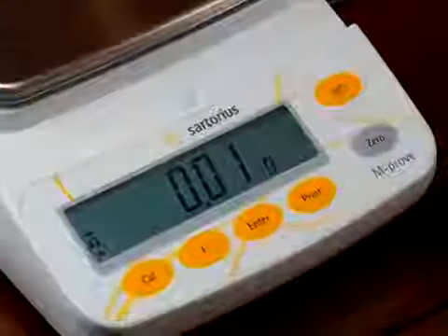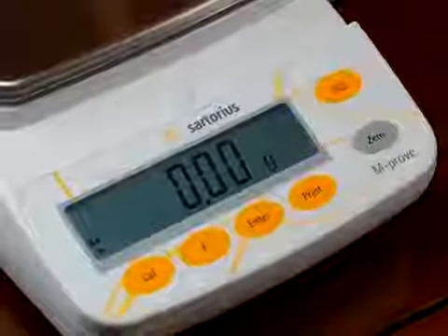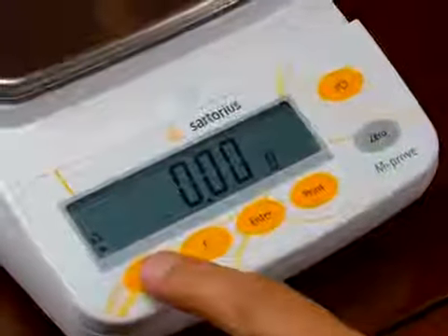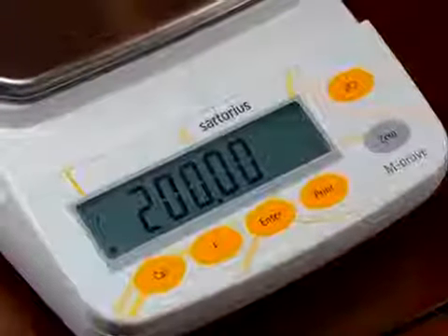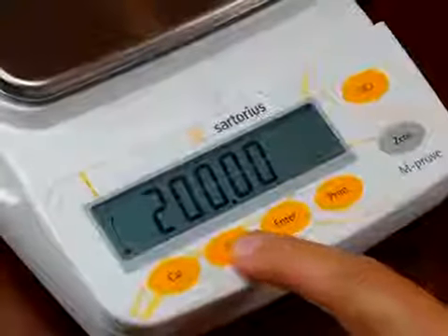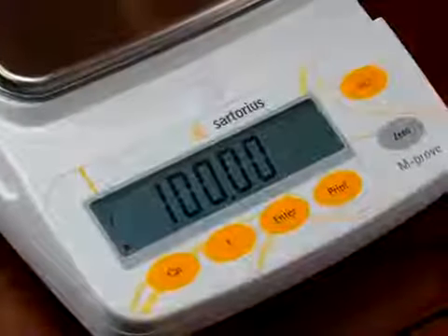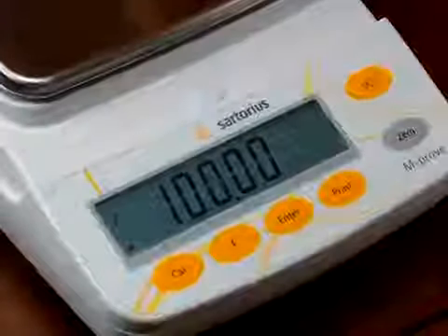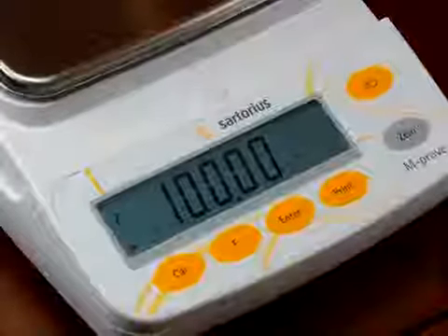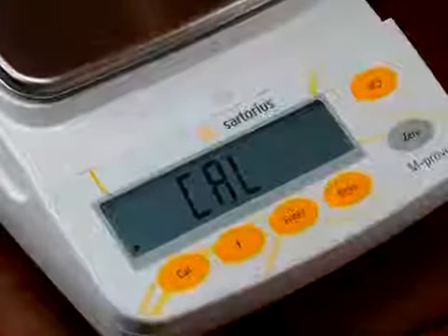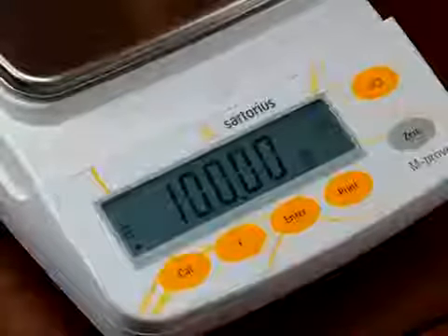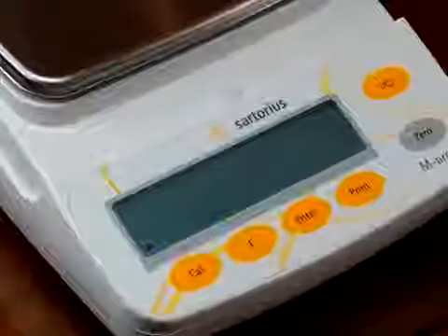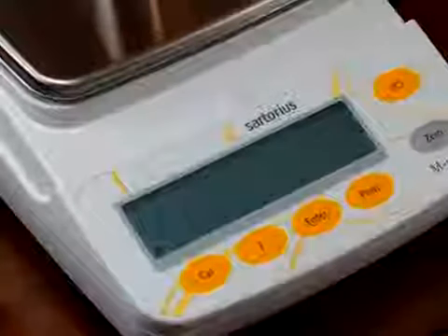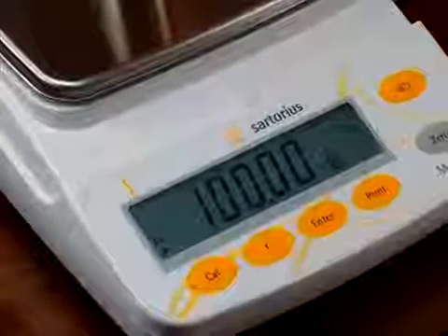Let me show you how to calibrate the balance real quickly using 100 grams instead. If we press the cal key again, the balance shows 200. This time we'll press the F key and we'll set it to 100. Where it reads 100, we want to hit the Enter key, so it's going to store the 100. Now it's showing 100. This time, just to show you how errors can happen, we'll put on the 200 grams. If we put on the 200 grams, the balance is not going to accept it. It will end up showing an error.